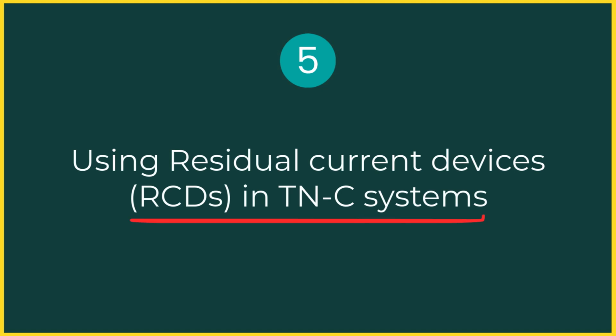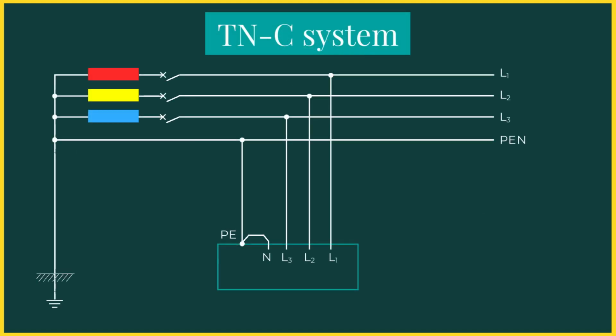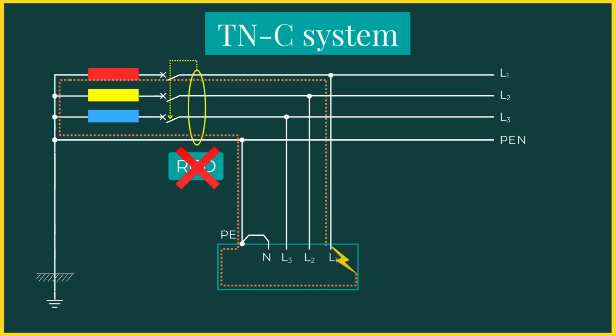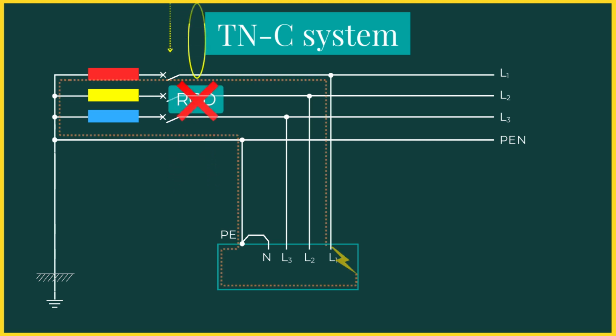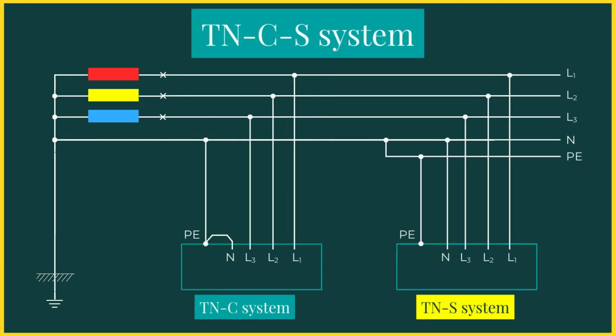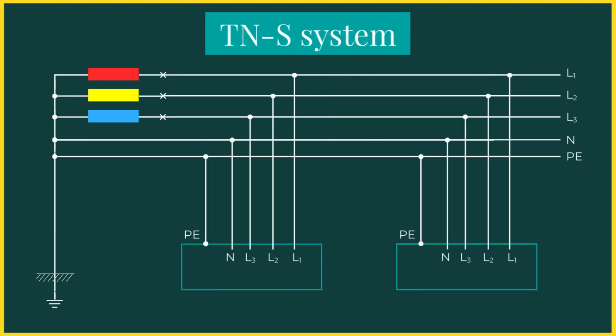Mistake 5. Using RCDs in TNC systems. Residual current devices cannot be used in TNC systems because the neutral and protective functions are combined into a single conductor. An RCD cannot correctly detect a residual current. As a result, RCDs are not permitted in TNC systems. If RCD protection is required, the system must transition to TNCS or TNS in accordance with IEC 60364.